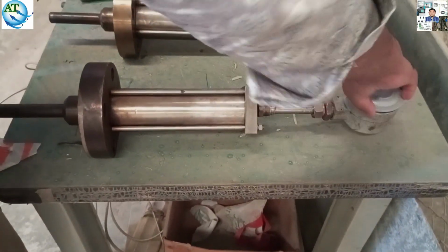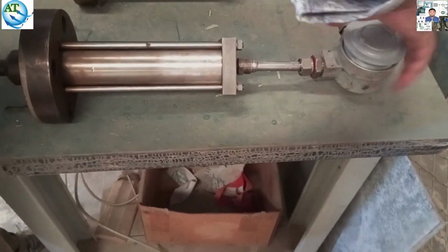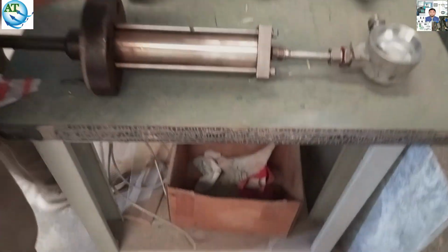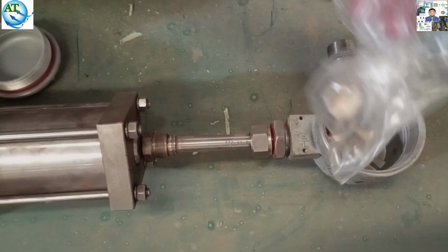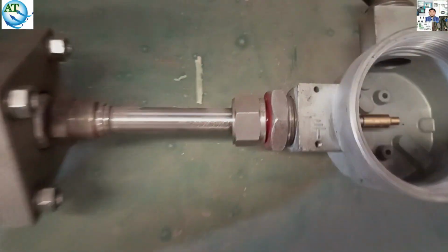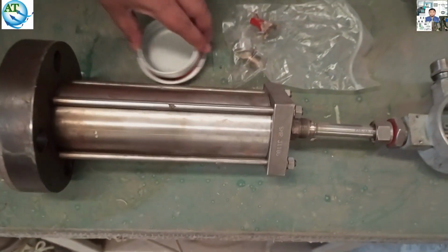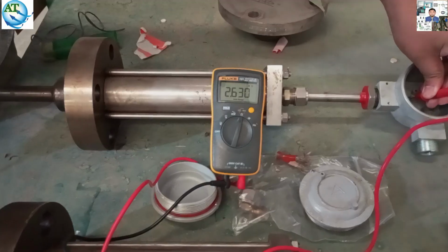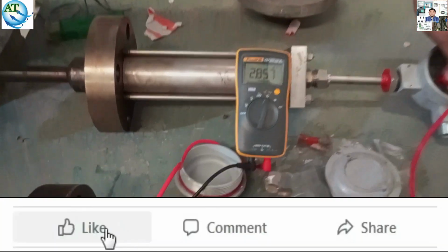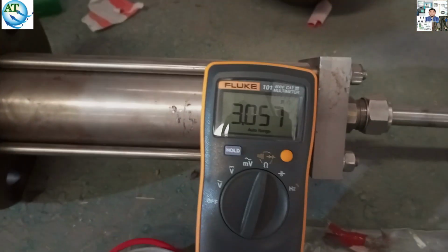You see, we are opening the top cover of this one. We want to check whether the igniter is okay or not okay. So you see, it is the head of this igniter. We use the multimeter to measure whether this igniter rod is okay or not okay. So you see, we are measuring and find that it is nearly 2.6 mega ohms.